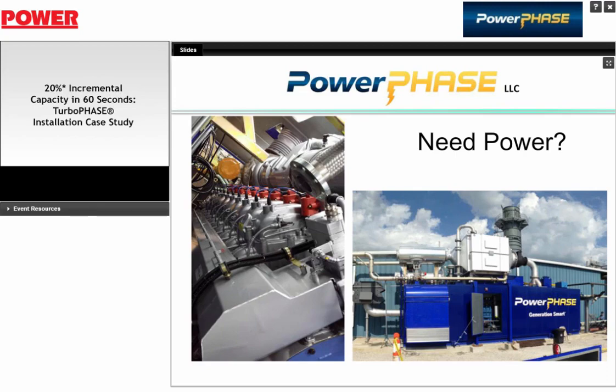But anyways, you have to have multiple units on these bigger gas turbines. But what that does is it gives you a much higher reliability factor. So, we did some reliability analysis, and we're working on some more detailed analysis on that. And say you have a 2-on-1 7FA, and you got 10 modules sitting there. And I didn't talk about, we have a little peak button on our module, so it'll let you put 10% more airflow out. So if one happens to go down, you still can get the output from 10. It's not like an all or nothing. And then you can spread it across any gas turbine in your power plant. So it really helps the reliability part.